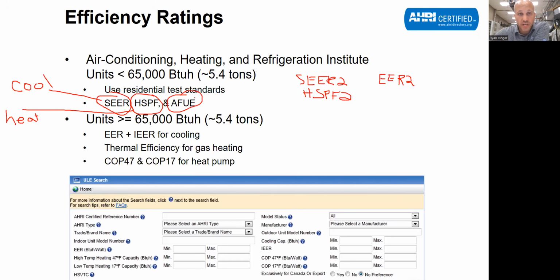AFUE, annual fuel utilization efficiency, is for gas heating, either a gas furnace or a gas boiler, right? How efficient are those guys? So a regular cooling system, you'd have a SEER, or nowadays a SEER 2, an EER2, and an AFUE. If it was a heat pump, you'd have a SEER 2, an EER2, and HSPF2. If it was a dual fuel system, you'd have a SEER 2, an EER2, an HSPF2, and an AFUE. All those different metrics represent how efficient each of those pieces are.